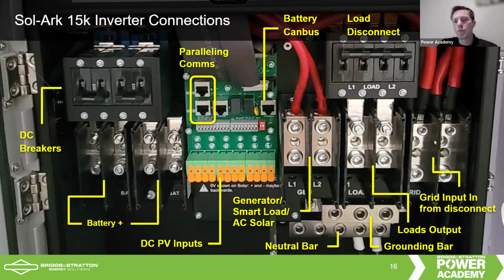And then you've got your input from grid coming in here on the right-hand side. You can fit up to 4-aught. Or 3-aught at least, I think. I think you can fit 4-aught because you can bring aluminum into this, so you can fit 4-aught for your 200 amp aluminum. Or if you're using copper, you'd probably be bringing 3-aught here.